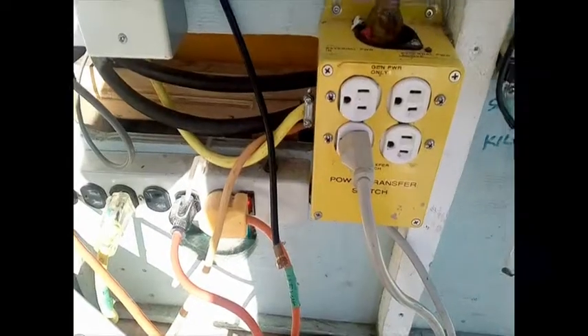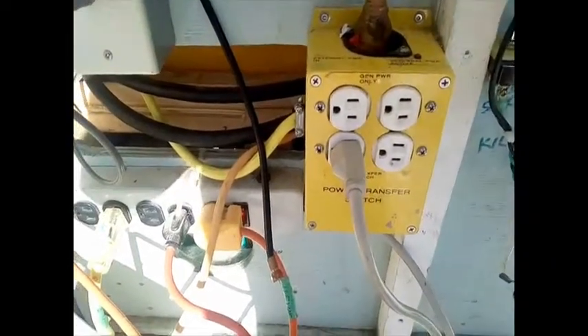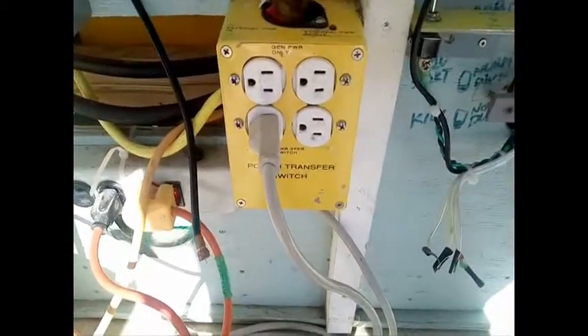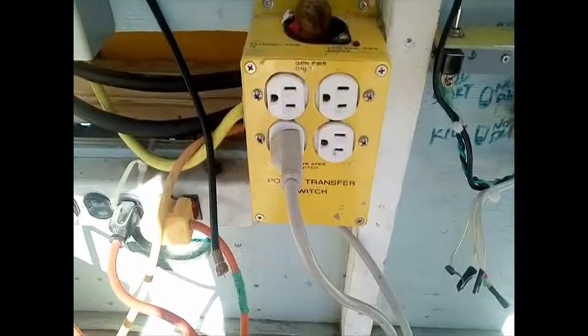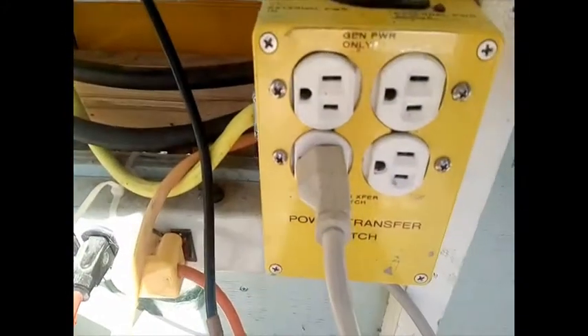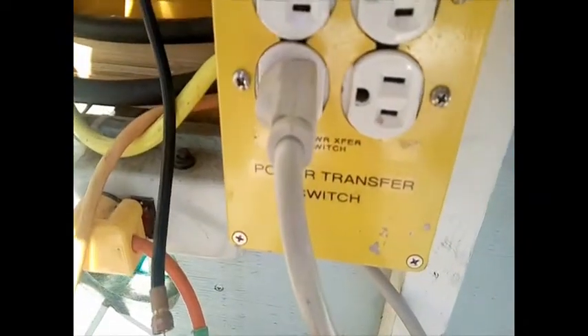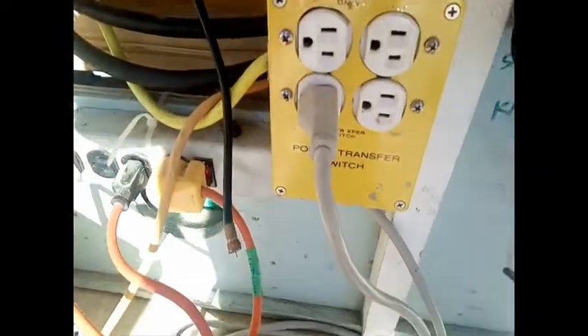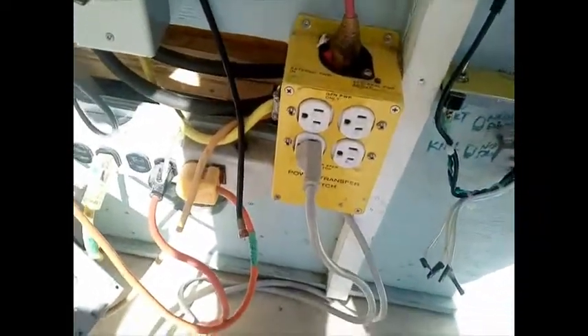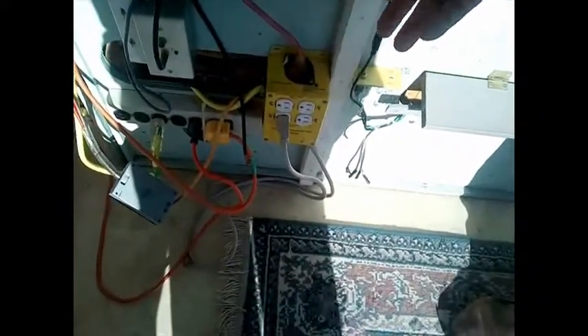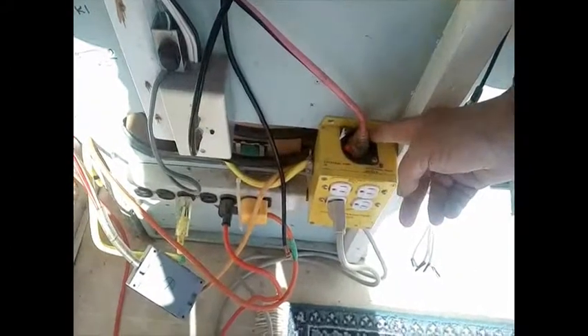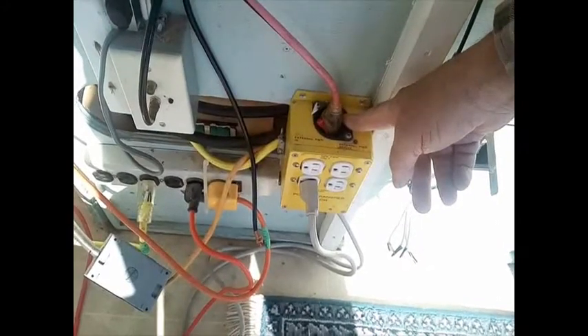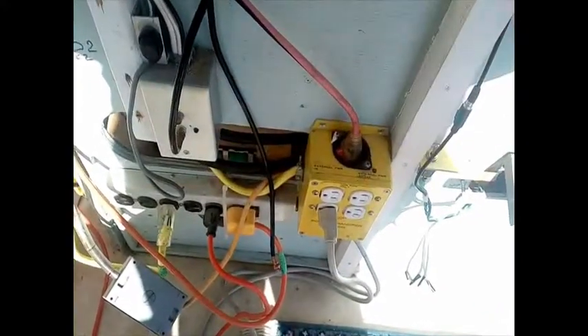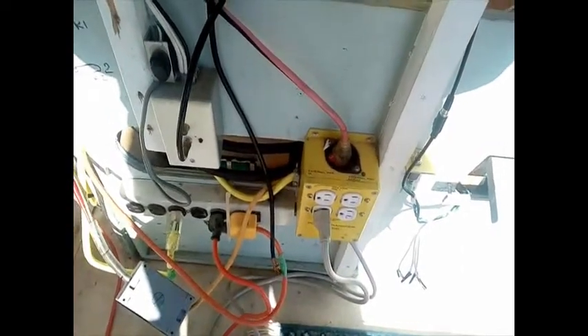This yellow box is a power transfer relay. There's two modes. One is the solar power through the inverter, and the second mode is the generator or outside power. This will switch over. External power comes in through the top, and this will energize the relay coil and switch it over to external power. If you disconnect this, the relay will fall back over onto battery power.